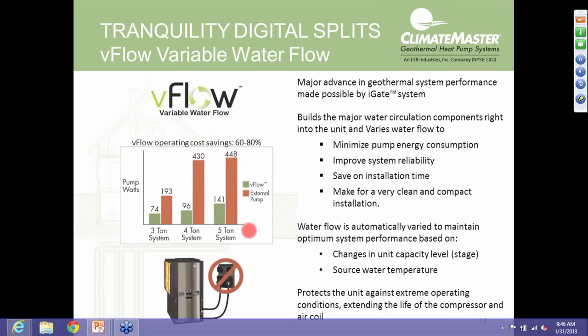Well, those pumps, again, they run anytime the heat pump's running. Those pumps are pulling 448 watts of power. To get the same flow rate through our variable speed pump, we're talking 141 watts. So again, significant pump watt savings can be had with the VFlow variable speed pump option.